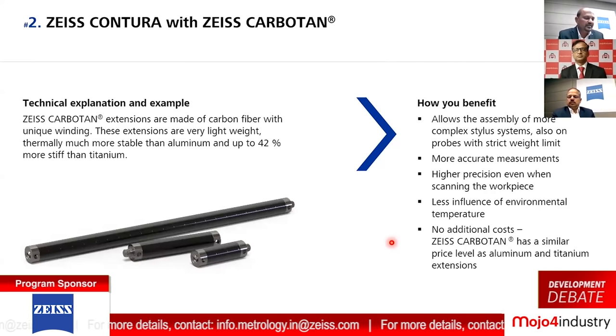The temperature effect on the stylus would be very minimal - this is a special material being used, and because of this it is very lightweight and also very immune to temperature variations. It is very stiff, and because of that you can ensure high speed measurement without any sacrifice in accuracy or repeatability of the measurements you're doing.